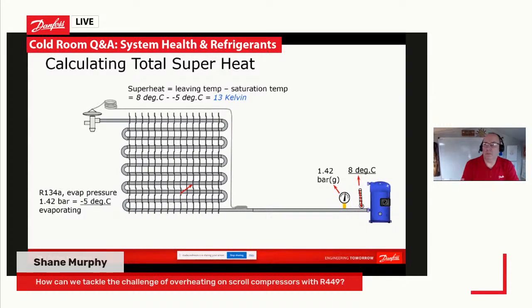So the other thing we need to do, we need to measure our superheat on our evaporator, but we also need to measure our total superheat on our system. And you can see there, very similar to what we had up before, we've got our evaporator, we've got our expansion valve, our filter, and the same thing, evaporating 134A, 1.42 bar, -5. And then to measure our total superheat, we need to measure the temperature basically at the suction stub of the machine. And you can see there that we are measuring 8 degrees C. So we've got 13 Kelvin total superheat on our machine. Absolutely fine. That compressor will live a nice, long and happy life.